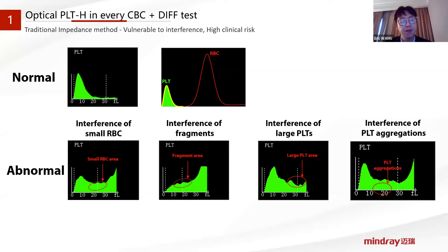Based on this 3D SQA platform, we developed new technologies and new parameters — the PLT-H. Getting accurate platelet counts is critical for disease diagnostics and treatment. There are many different platelet counting methodologies on the market. Mindray has developed our patented PLT de-aggregate function to solve platelet counting problems. Many studies and past experience have shown that analyzers using traditional impedance methods sometimes cannot provide reliable platelet counts, especially when facing interference from small red blood cells, fragmented red blood cells, large platelets, and platelet aggregations — giving falsely high or falsely low results.